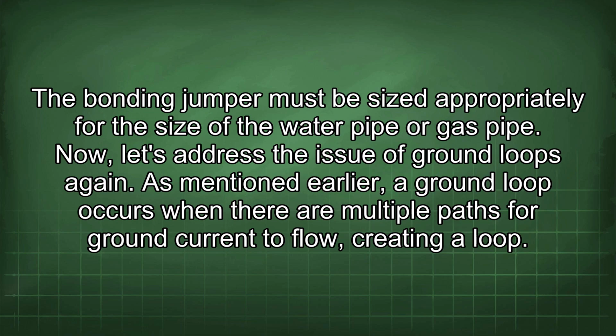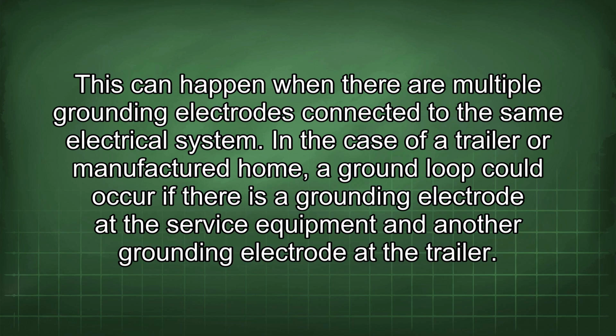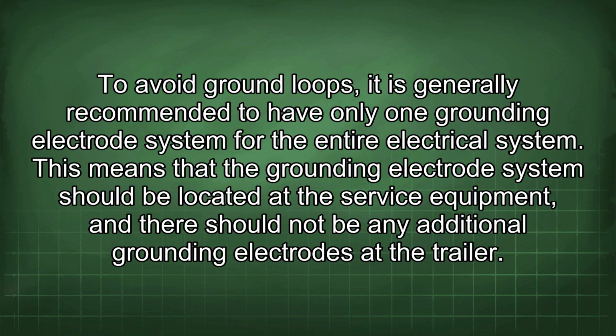Now let's address the issue of ground loops again. As mentioned earlier, a ground loop occurs when there are multiple paths for ground current to flow, creating a loop. This can happen when there are multiple grounding electrodes connected to the same electrical system. In the case of a trailer or manufactured home, a ground loop could occur if there is a grounding electrode at the service equipment and another grounding electrode at the trailer. To avoid ground loops, it is generally recommended to have only one grounding electrode system for the entire electrical system. This means that the grounding electrode system should be located at the service equipment, and there should not be any additional grounding electrodes at the trailer.